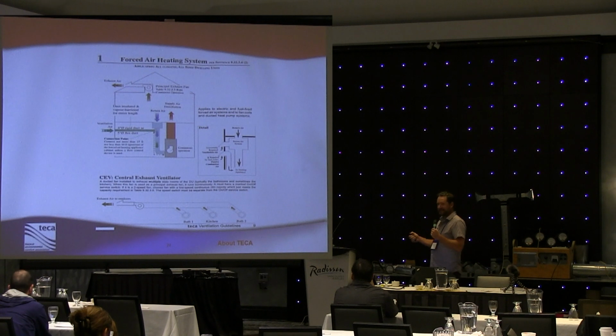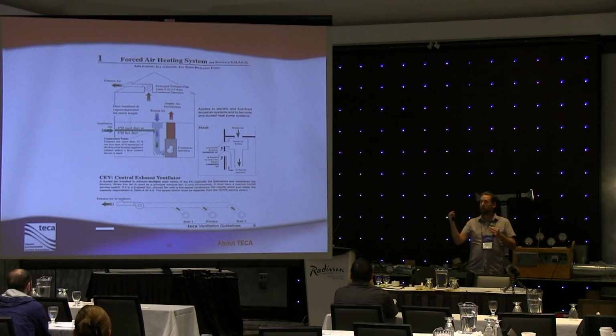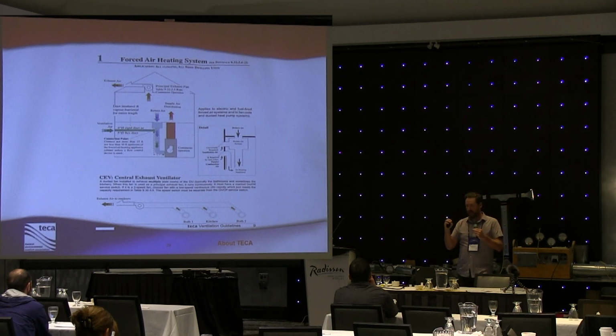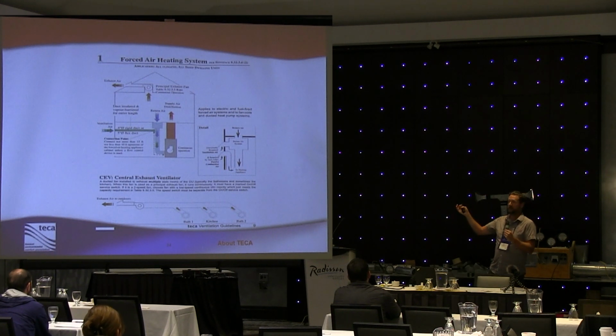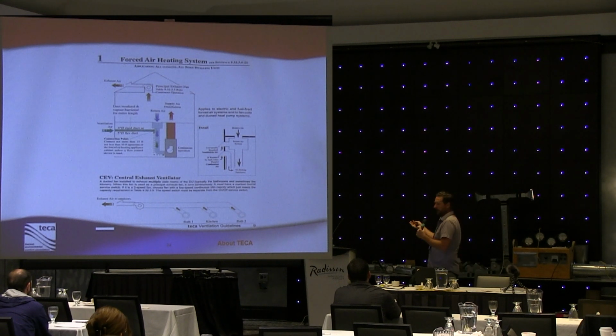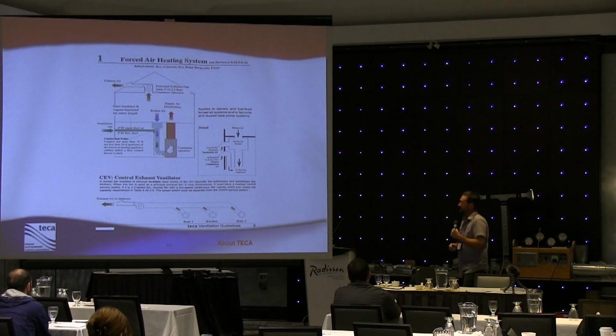There are some fans out there that are available that will be able to be set up to run at the prescribed ventilation rate, which may be very low. If it's a small building, the rate of ventilation may only be 35 cubic feet per minute. It's a very, very small ventilation rate. However, the building code prescribes that a bathroom must have a minimum of 50 CFM in an intermittent capacity.